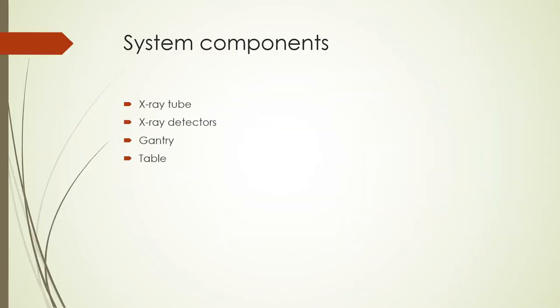Let's look at the X-ray system components. The main components are: the X-ray tube, usually a high-power tube of 60 kW or higher; X-ray detectors; a gantry; and a patient table. We shall learn about each of these components in the next few slides.